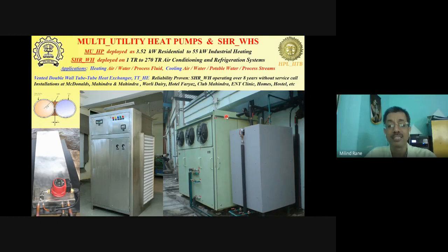And evaporatively condensing the refrigerant, as you may know, allows you to reduce the condensing temperature to the lowest possible extent as compared to air cooled, then tower water cooled, and then best is the evaporative cooling. So evaporative cooling gives you the lowest condensing temperature. Lower condensing temperature helps you reduce the condensing pressure. Reduced condensing pressure reduces the compressor power required, and so your COP increases because of that. And reduced condensing temperature also reduces the refrigerant temperature coming out of the condenser. So that also helps you improve the cooling effect per unit refrigerant circulated because of reduced flashing. So because of all these reasons put together, this multi-utility heat pump with evaporative condensation enabled us to save around 25 to 36% of energy using this particular system.